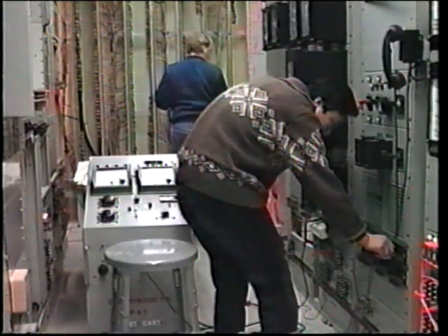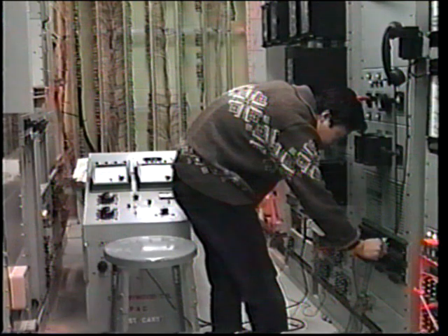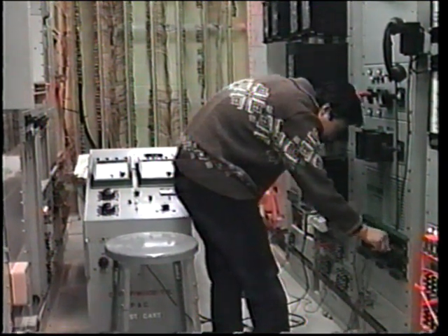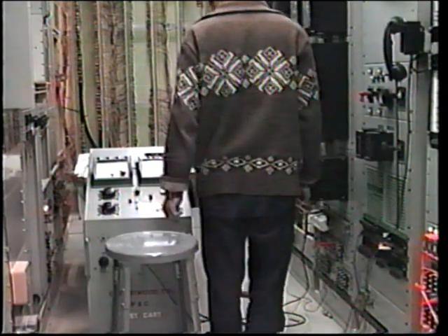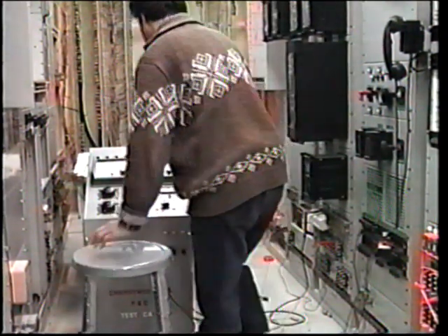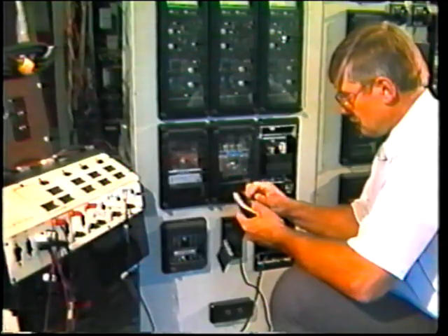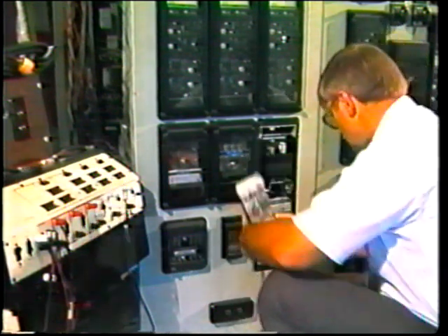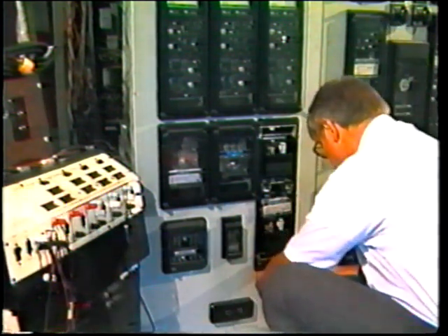Once again, we see the problem here of incorrect wiring and incorrect setting of relays. These problems should likely have been picked up during the commissioning and acceptance tests of the equipment. Clearly, it is essential that such tests be performed after any installation work has been carried out. Another problem is that this defect would not have been discovered if the fault had not occurred. We know that faults are very rare, and some protection equipment has never actually operated under true fault conditions. This is the reason that routine testing of every protection scheme must be carried out at regular intervals.